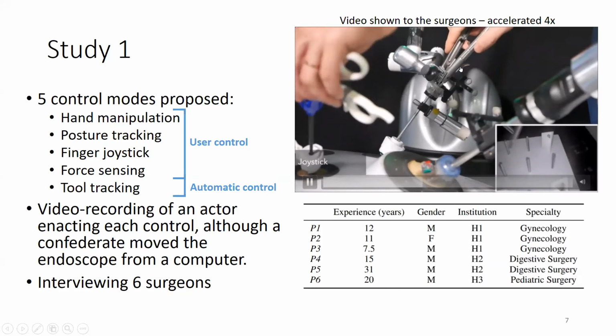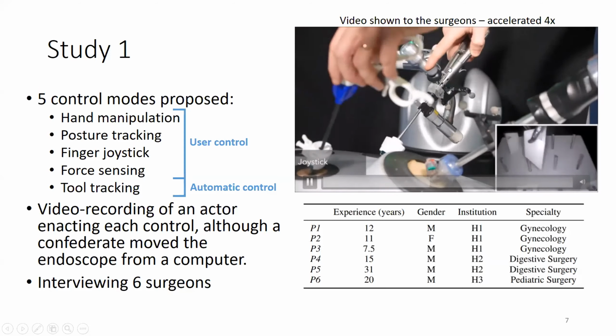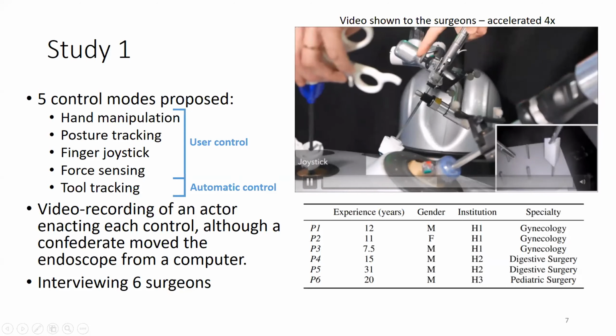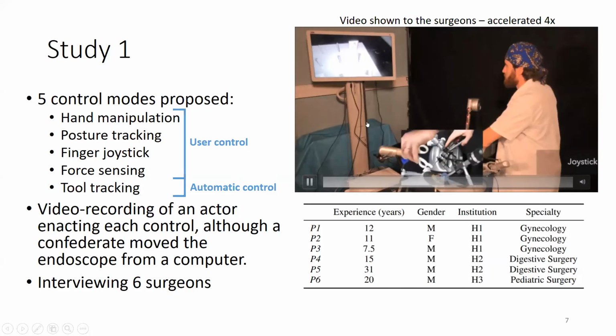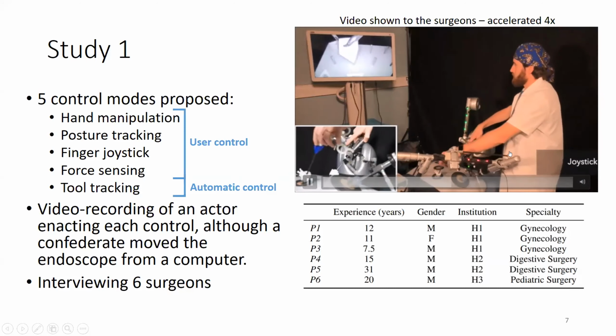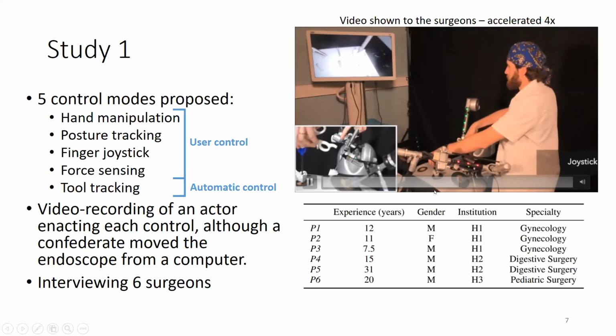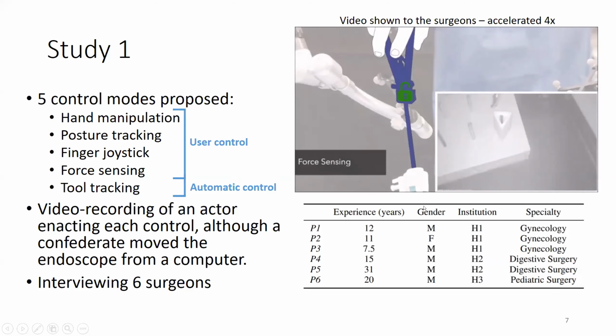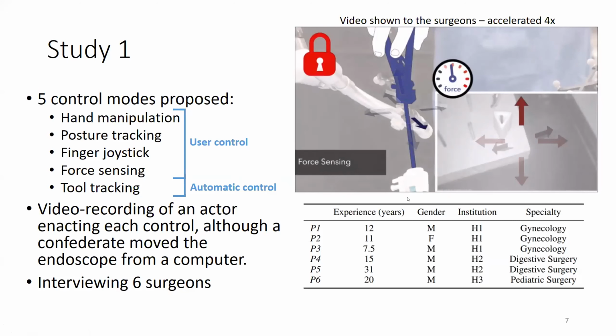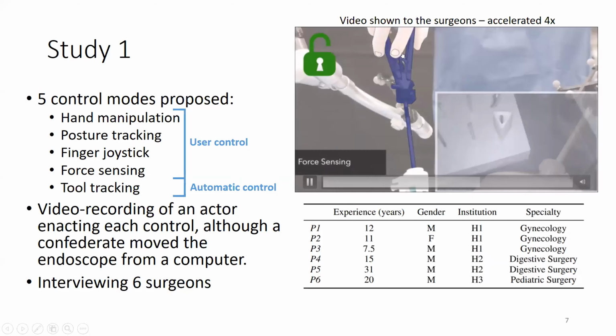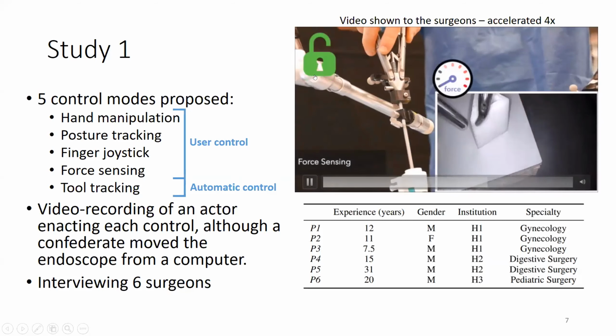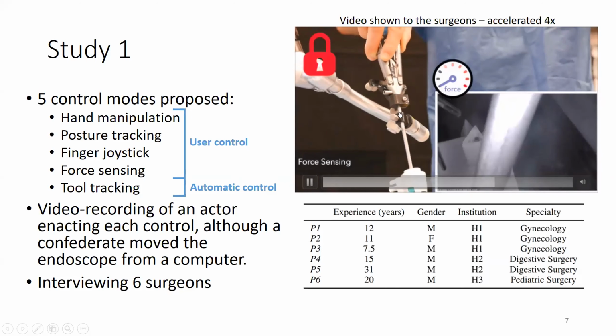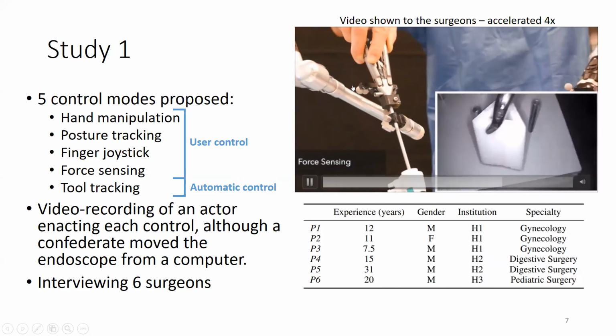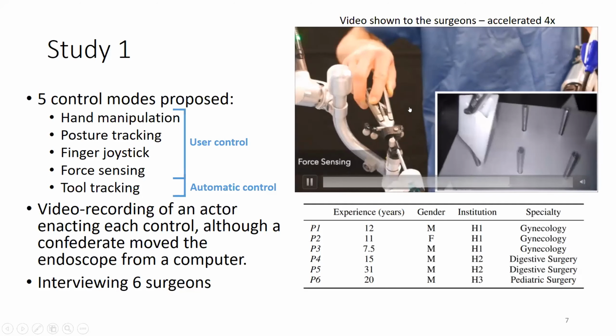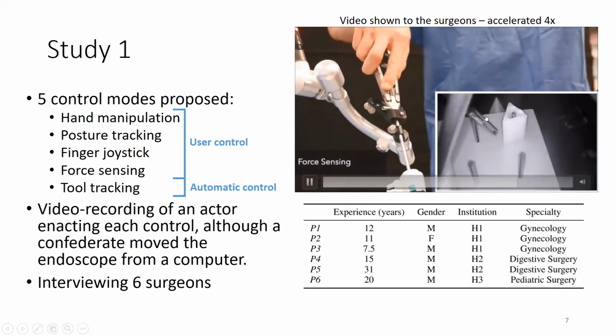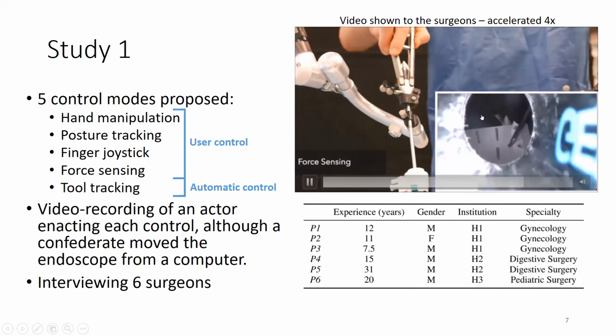The third mode is to use a joystick. This is sometimes used in some commercial products, a joystick attached to the instrument that controls the endoscope position, as shown right now. We had a fourth system, which is force sensing. With this system, the endoscope holder is locked with a high stiffness, and when the surgeon moves, it creates a velocity on the endoscope. So it's the force-to-velocity paradigm between the instrument and the endoscope.